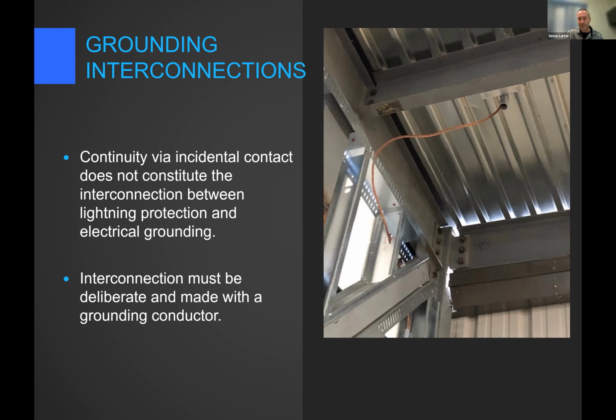A water pipe, an electrical conduit, if it's near enough our conductor that we have to bond it like a metal body of inductance, that's incidental contact too. But that is not the deliberate grounding interconnection that must be made at or below grade. All of those are incidental. All of those are not specifically supposed to be the interconnection with the electrical ground. So that doesn't count as the interconnection.